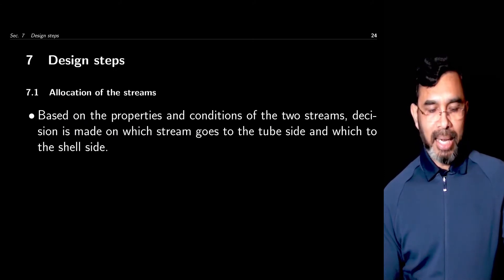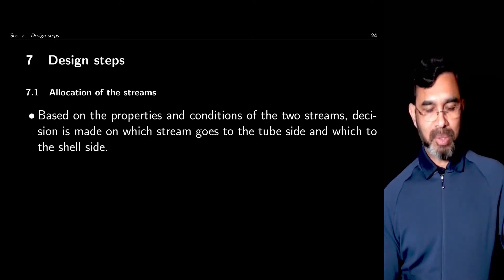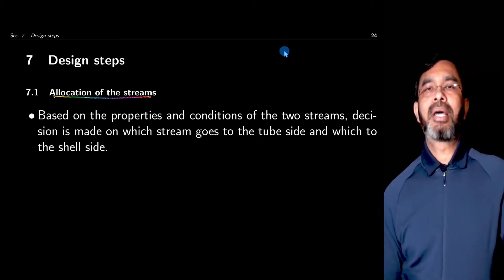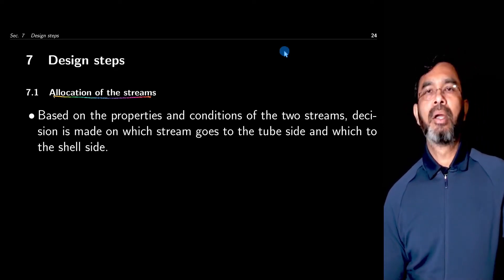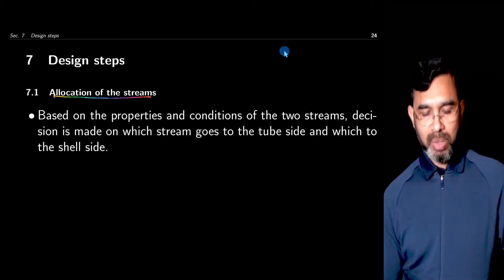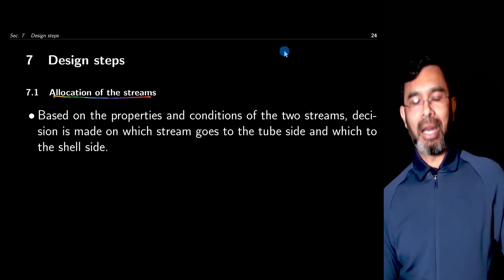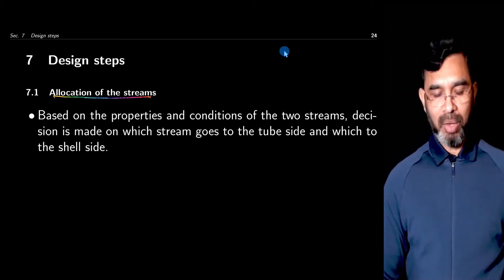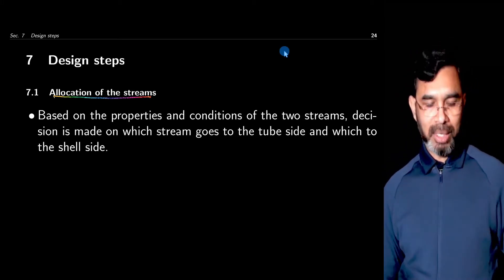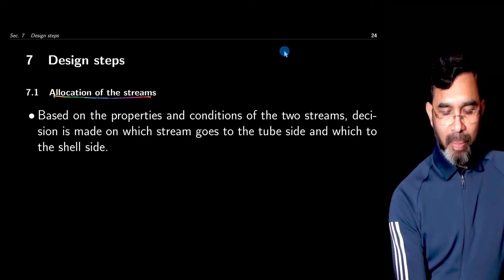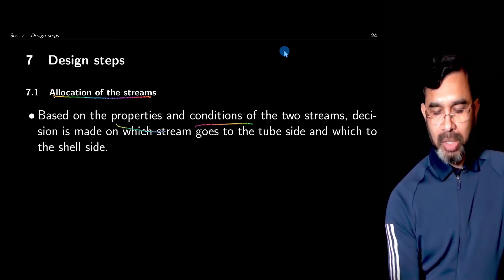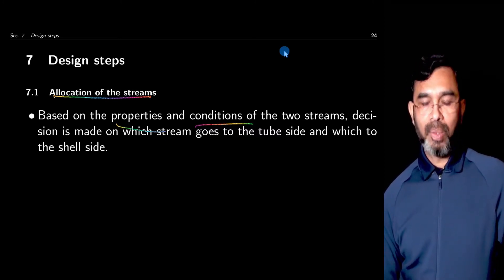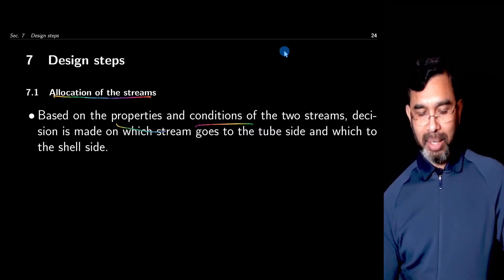Typically the designs are carried out in well-defined steps. First, you start with the allocation of the streams. For a double pipe heat exchanger, you decide which stream goes to the annulus and which goes to the inner pipe. For a shell and tube exchanger, you decide which stream goes to the shell side and which goes to the tube side. That all depends on the properties and conditions of the two streams. So the first step is to decide which stream goes to what side.